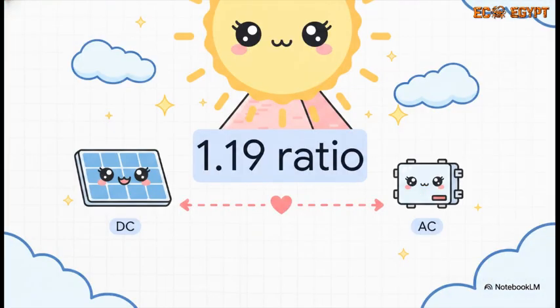And check this out—our 1.19 DC to AC ratio is not a random number. It's engineered specifically for Egypt's unique irradiance profile, hitting that sweet spot to ensure we don't clip too much power at peak hours while maximizing inverter use all day long.